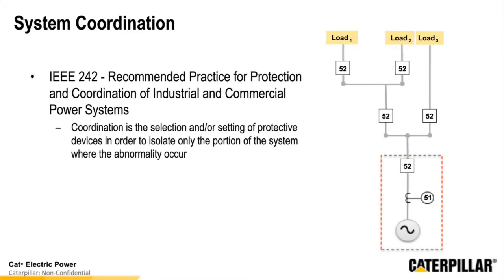So let's talk about what a coordination study is. The IEEE Standard 242, Recommended Practice for Protection and Coordination of Industrial and Commercial Power Systems, is really the overarching document that gives good instruction on what a coordination study is, how to perform a coordination study, and what the different things and considerations are that you might have with things such as your transformers or fuses or other parts of the system. So I highly recommend that as a more complete document than what we're going to cover today. Overall, the IEEE standard discusses coordination as the selection and/or setting of protective devices in order to isolate only the portion of the system where an abnormality occurs.